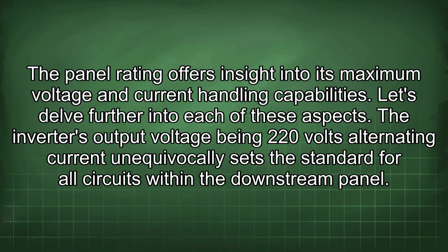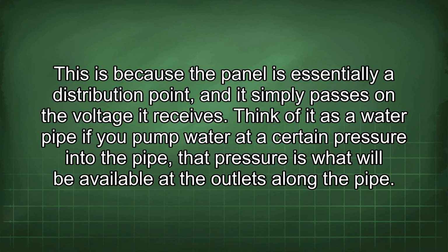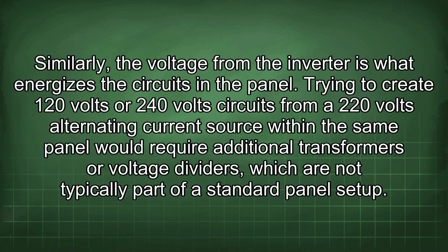The inverter's output voltage being 220 volts alternating current unequivocally sets the standard for all circuits within the downstream panel. This is because the panel is essentially a distribution point, and it simply passes on the voltage it receives. Think of it as a water pipe. If you pump water at a certain pressure into the pipe, that pressure is what will be available at the outlets along the pipe. Similarly, the voltage from the inverter is what energizes the circuits in the panel.